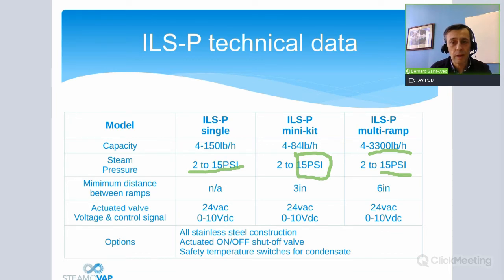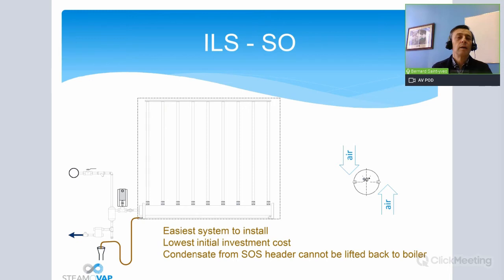So let's look at the SteamOsorb system. The SteamOsorb system is basically the same way to distribute the steam inside the air handling unit or the duct as we use with atmospheric steam. Atmospheric steam is steam coming from an electric steam humidifier. We are working with electric steam humidifiers below 2 psi. There is no pressure in this.